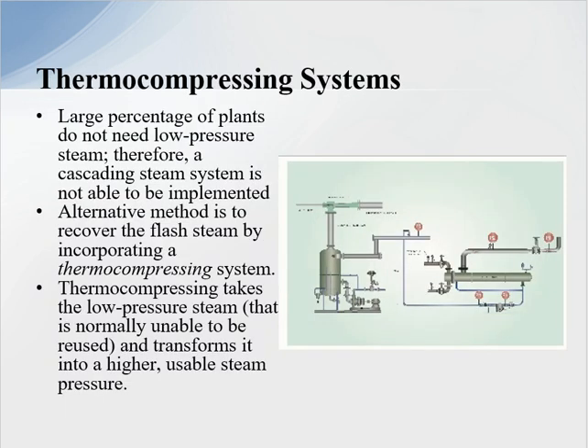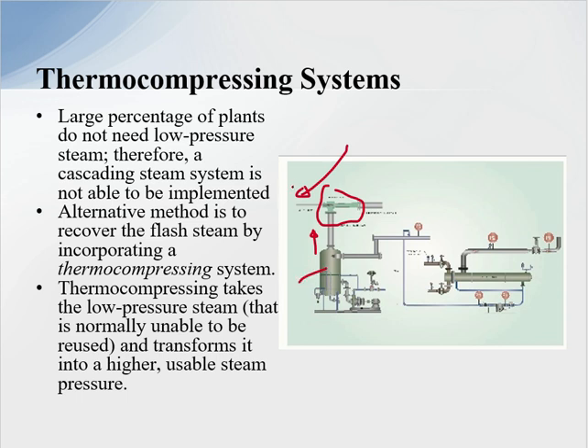The next application is thermal compressing. This is where we do not have a use for low pressure flash steam — therefore we use a thermal compressor to take the low pressure flash and bring it up to a higher pressure. Here is the thermal compressor system: this is the low pressure steam coming off of the flash tank, and we have a motive steam pressure at a higher level. For example, if the flash tank is at 30 PSI, our motive steam could be 150 PSI or higher, and we would produce 60 PSI intermediate pressure to go out into the system.